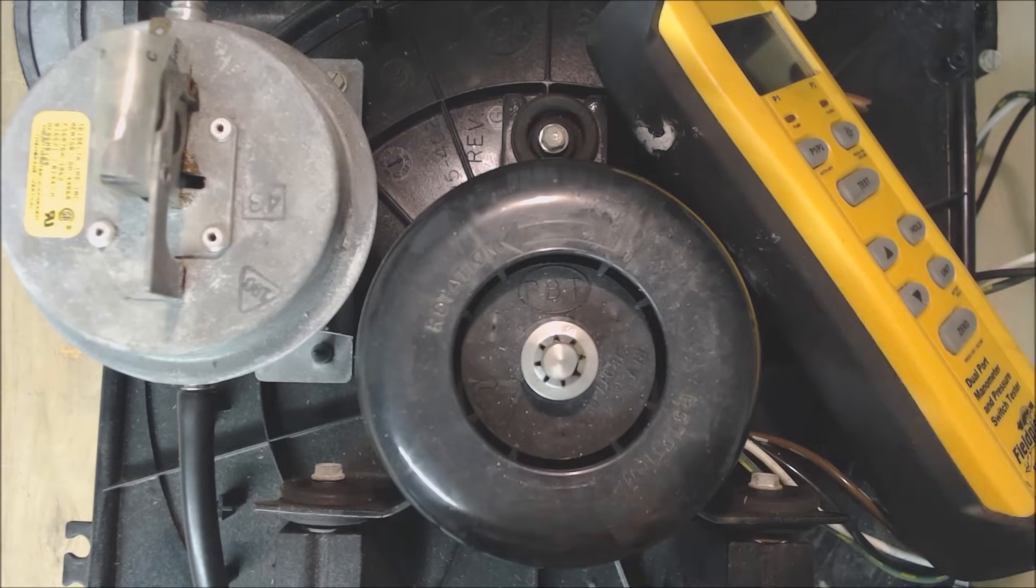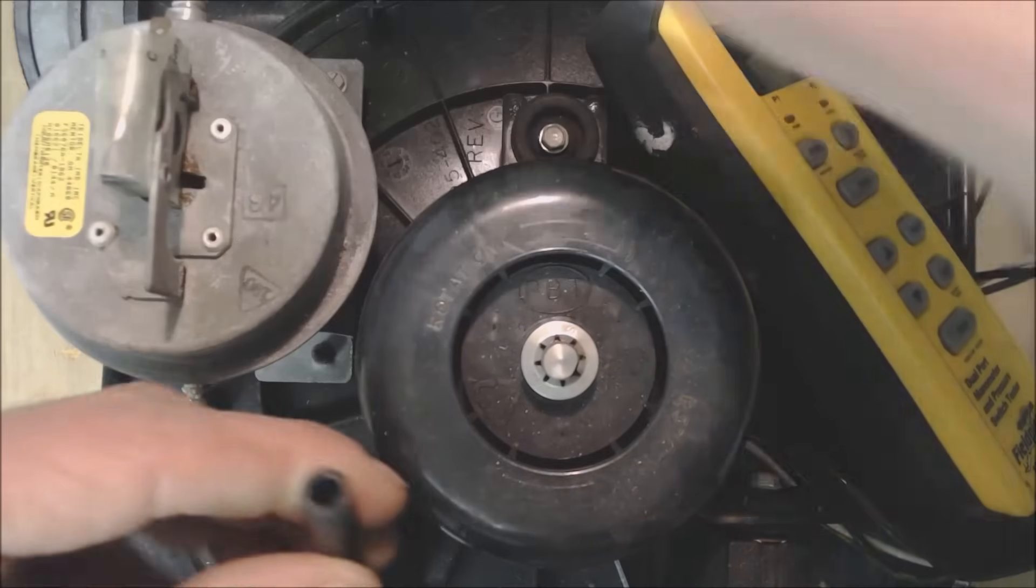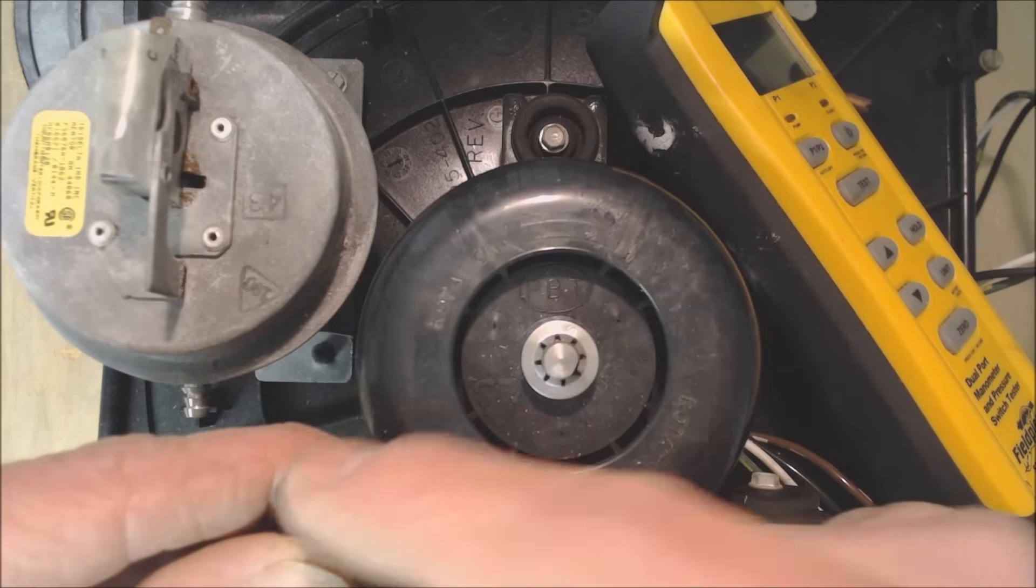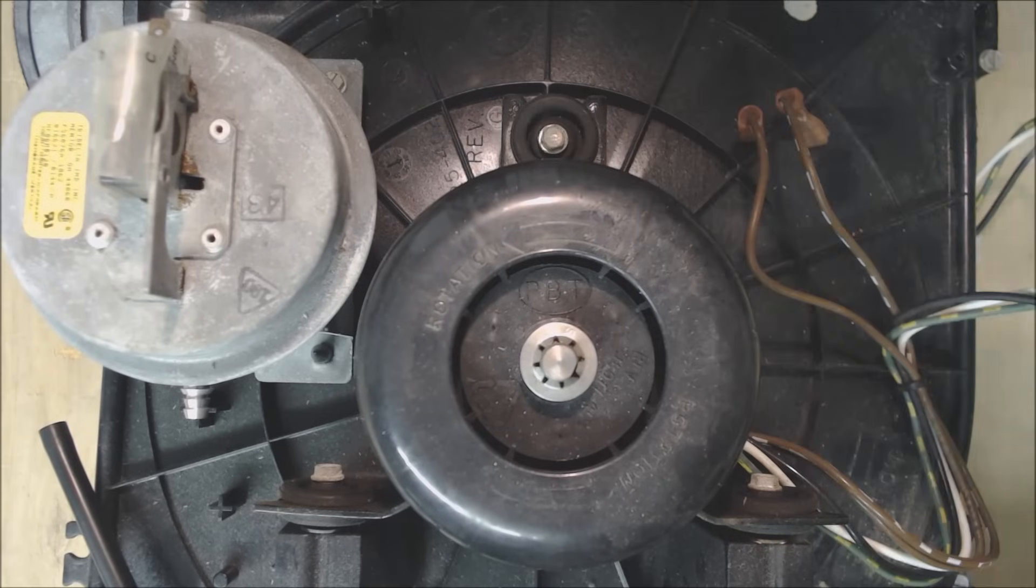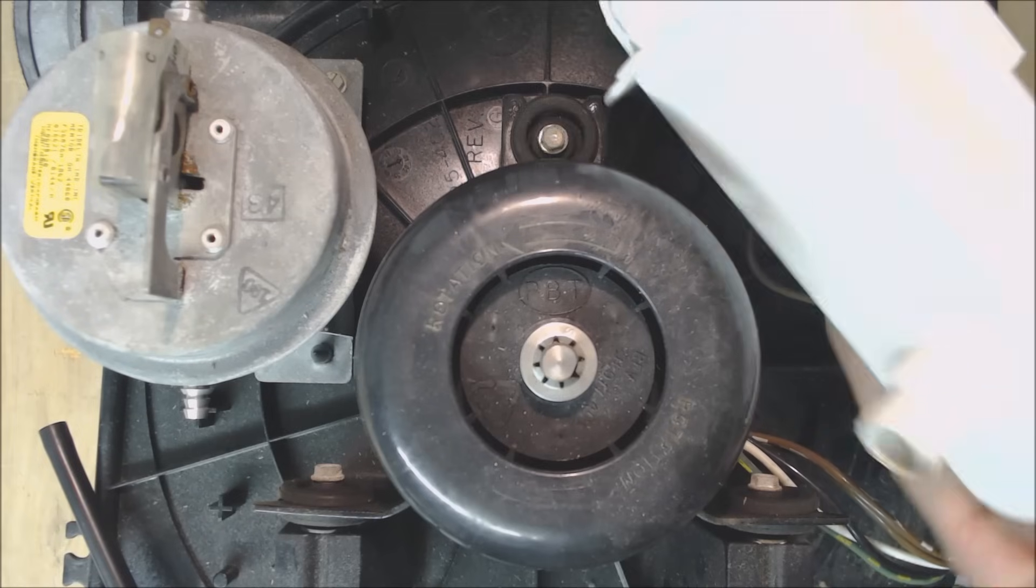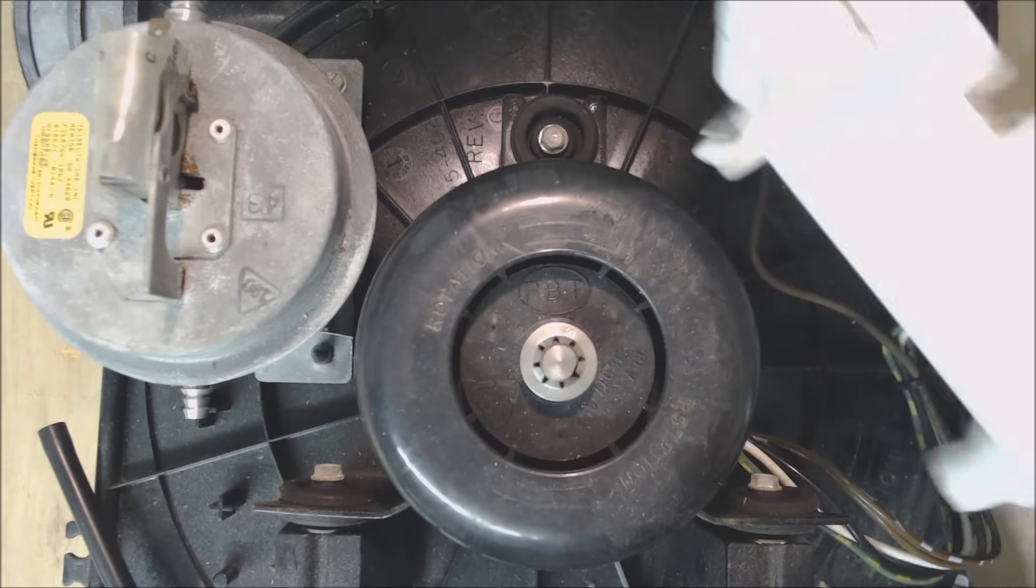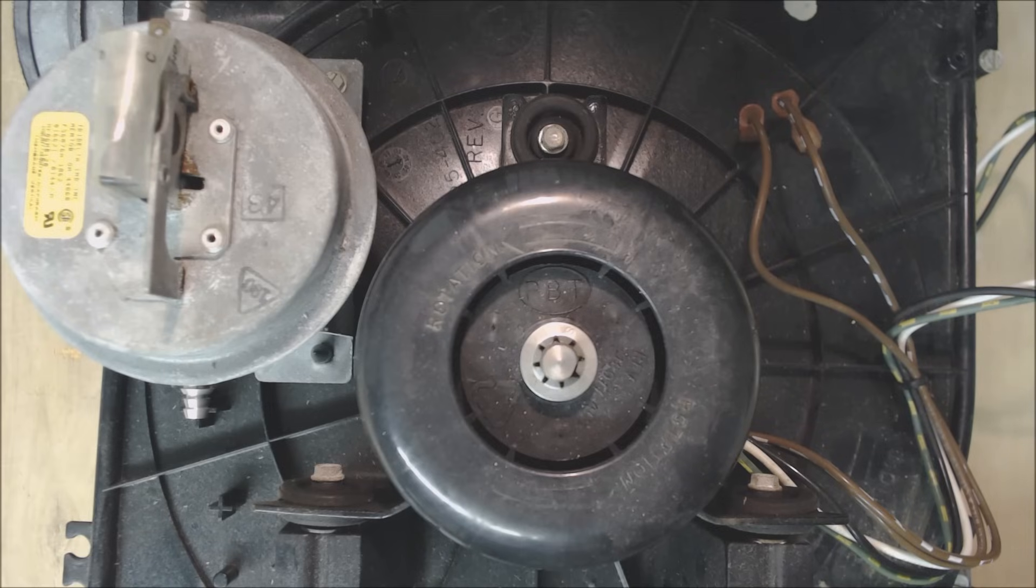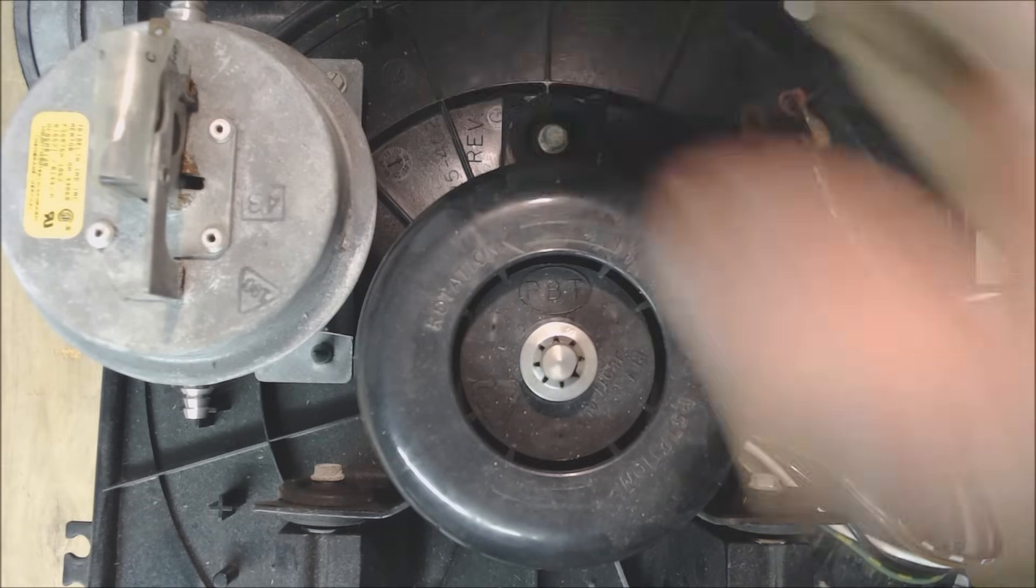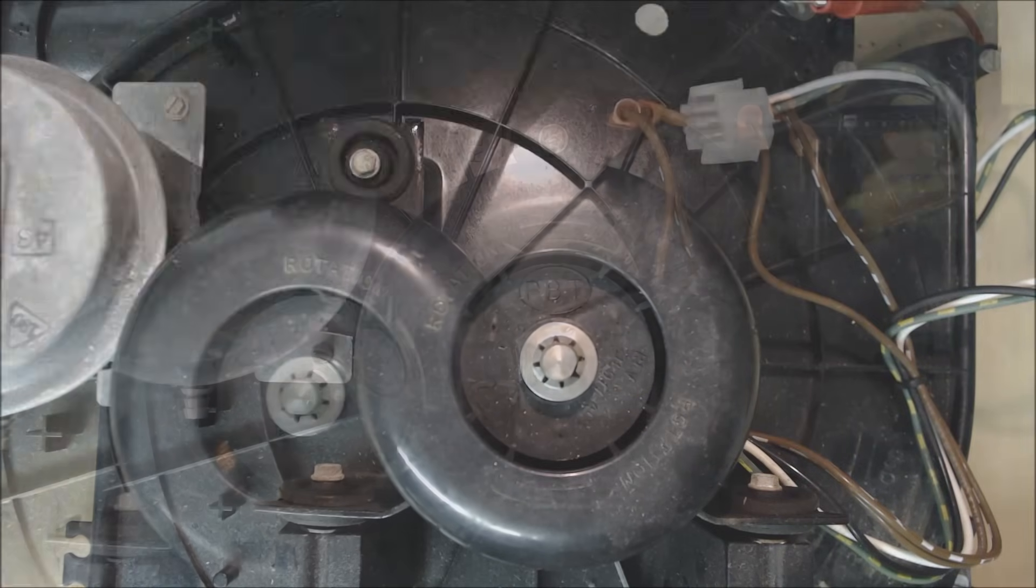As well, if you were going to go ahead and blow out these lines, make sure that you disconnect them from the pressure switch before you put any pressure on them. So then you can blow these out. You could have a problem if the pressure switch tests good. You could have a problem if maybe your condensate trap for your 90% efficient furnace, maybe that's clogged or maybe the drain piping is clogged or maybe the tubing like this tubing right here is clogged or maybe you have a clog in your exhaust or a clog in your intake. Possibly, maybe the heat exchanger is clogged and if that's the case, that's a very serious situation. You want to make sure that you go ahead and verify if that is clogged.